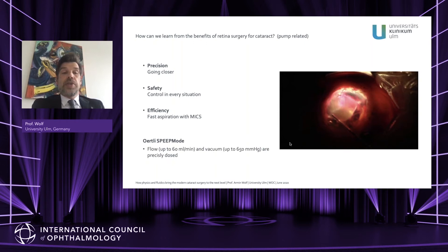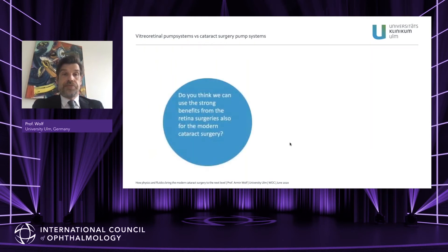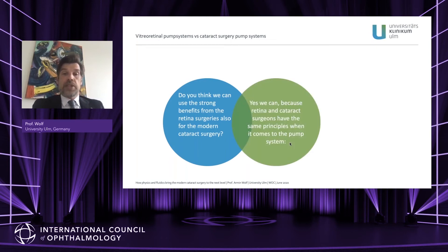The Oertli SPEEPmode has a flow of up to 60 milliliters and a vacuum of up to 650 mmHg, which are precisely dosed and can be controlled via foot pedal or pre-settings on the machine. The question is, what can we learn from vitreoretinal pump systems and implement into cataract surgery? I believe we can, because both retinal and cataract surgeons have the same demands: safety, efficiency, and high precision all at the same time.